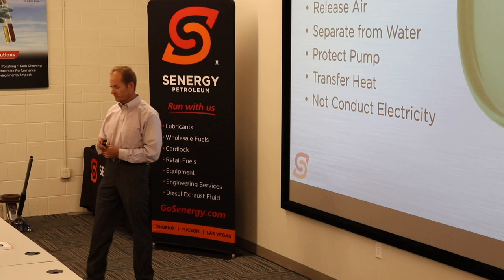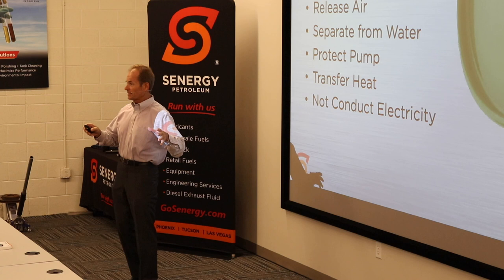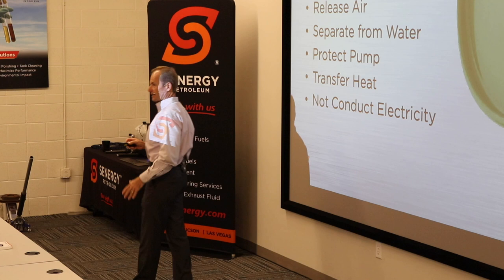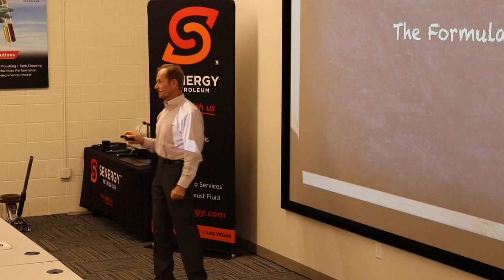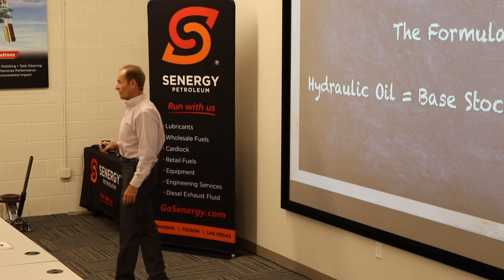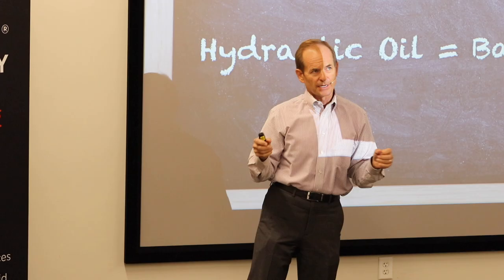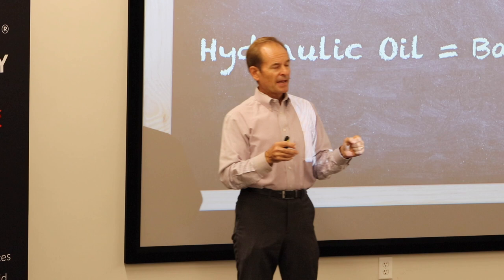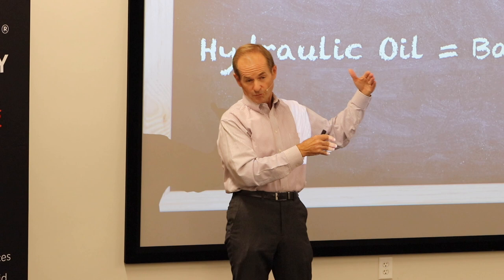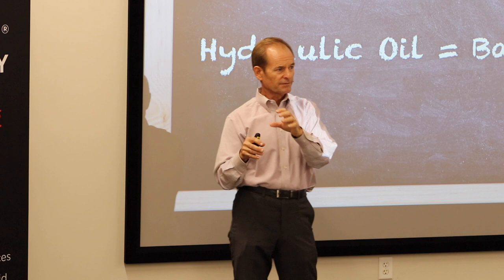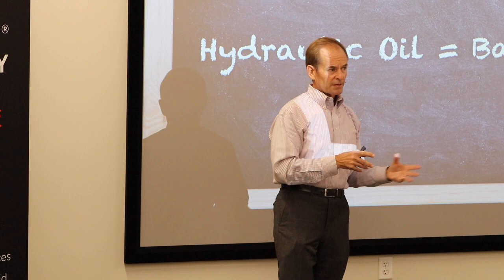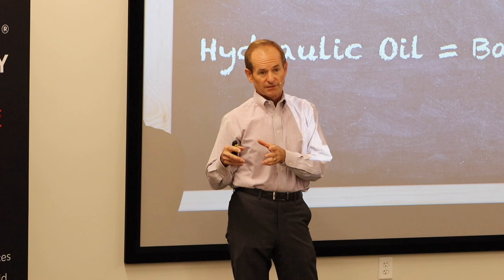Those are some of the things we're asking the oil to do for us. Now let's get into some details on what the oil is made of and how it does this stuff for us. Our hydraulic oil is base stock plus additives. Hydraulic oils differ from engine oils in that they have fewer numbers of additives and the overall percentage of additive is much lower — an engine oil can be 20–30% additives in a really high-end truck engine oil, whereas you're less than 5% additives in a typical hydraulic oil.